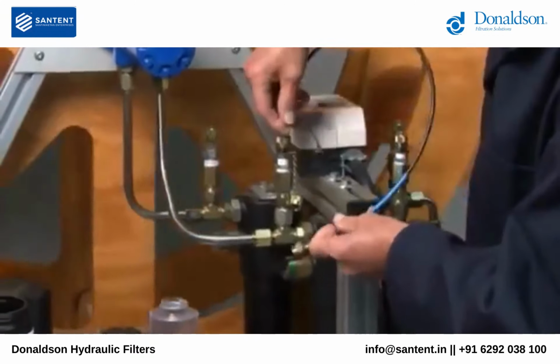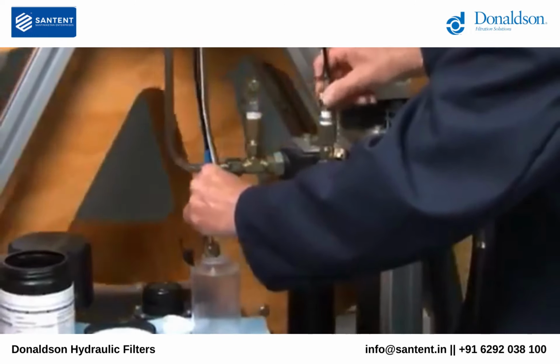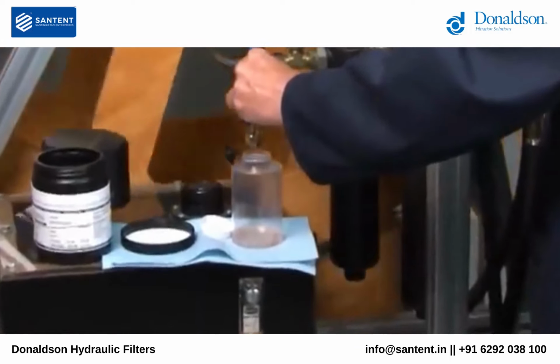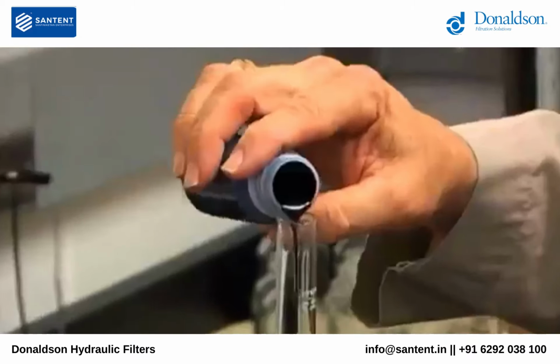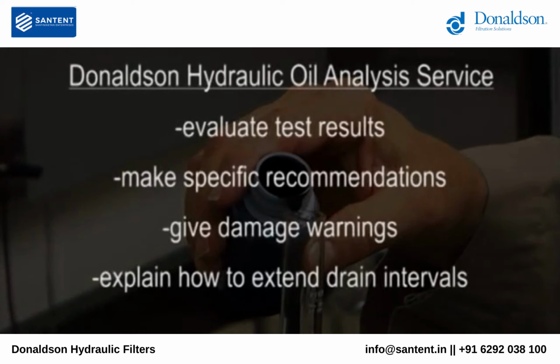Analysis of your hydraulic oil is another important part of protecting and maximizing the life of hydraulic systems. Hydraulic oil from equipment in regular use should be sampled at 500 hours or monthly. The Donaldson Hydraulic Oil Analysis Service, which is described in Module L6, includes an evaluating of the test results and specific recommendations and warnings of imminent component damage where warranted. You can also learn how to extend your hydraulic oil drain intervals.